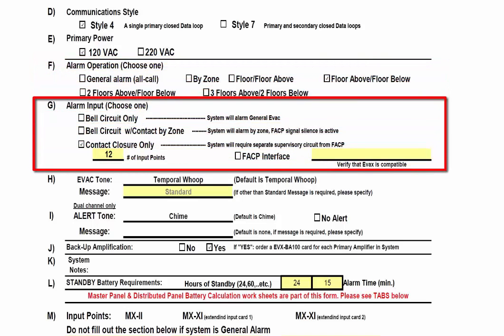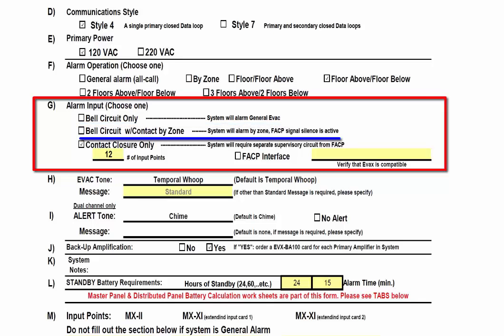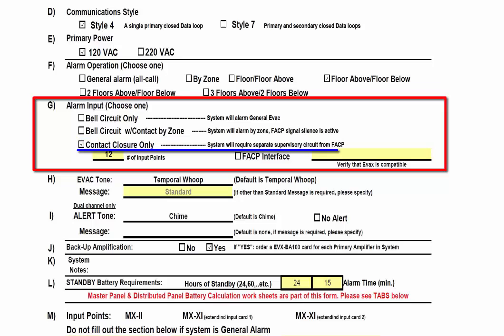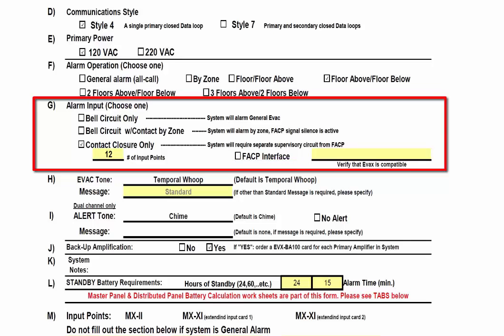In the Alarm Input section, we specify how the HMX system is intended to interface with the fire alarm control panel. Bell circuit only indicates a NAC circuit from the fire alarm panel will be used to trigger the HMX voice panel to signal a general alarm condition. Bell circuit with contact by zone selection requires both a NAC circuit from the fire alarm control panel and a programmable relay contact closure. You can also choose contact closure only, or you can choose fire alarm control panel interface. To use the fire alarm control panel interface, you will need to verify that the fire alarm control panel is compatible with the HMX panel by EVAX. Similar to alarm operation, you can only choose one alarm input.